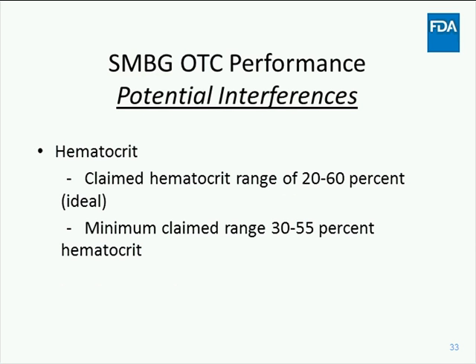As with the BGMS document, the effect of hematocrit on device performance should also be evaluated. However, here a claimed hematocrit range of 20 to 60 is considered ideal, since the intended user population may reasonably be expected to have hematocrit values between 20 and 60%. Now this document also lists a minimum claimed range that should be no narrower than 30 to 55% hematocrit. And in this SMBG document, the goal is to have a bias of less than 8% on average for the study for glucose concentrations greater than 75, with no individual value having greater than 15% relative to the comparator.